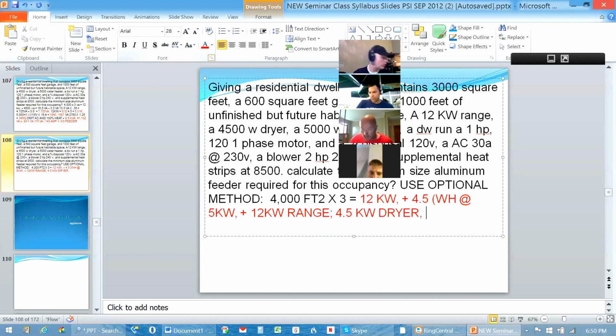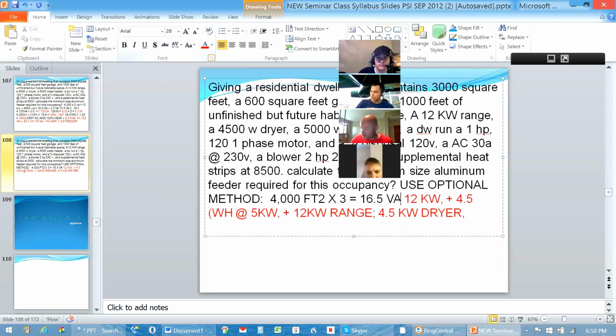And then under Part 4, I'm looking at water heaters, which I've calculated as a fastened-in-place appliance, so it's already included in there. So the first step was the 16.5 kVA for the lights and plugs, plus the 12 kW for the range, plus the water heater and dryer. The water heater was 5, and the dryer was 4.5.